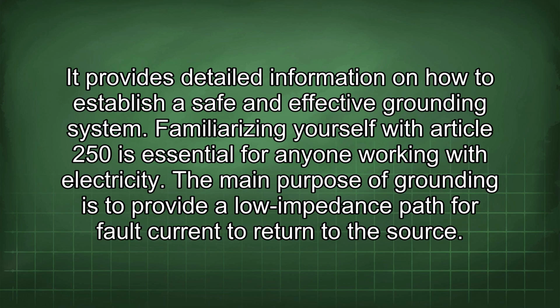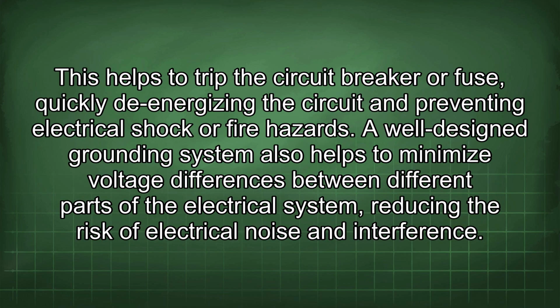The main purpose of grounding is to provide a low impedance path for fault current to return to the source. This helps to trip the circuit breaker or fuse, quickly de-energizing the circuit and preventing electrical shock or fire hazards. A well-designed grounding system also helps to minimize voltage differences between different parts of the electrical system, reducing the risk of electrical noise and interference.